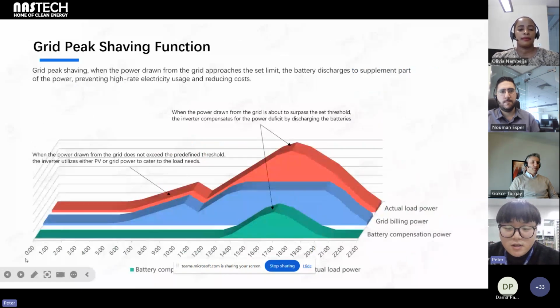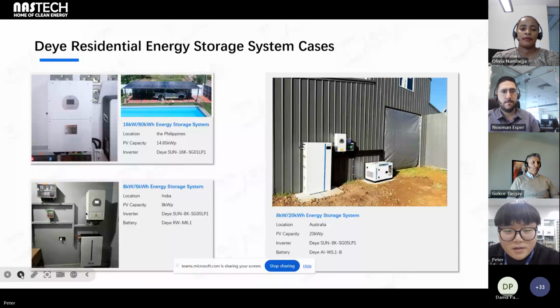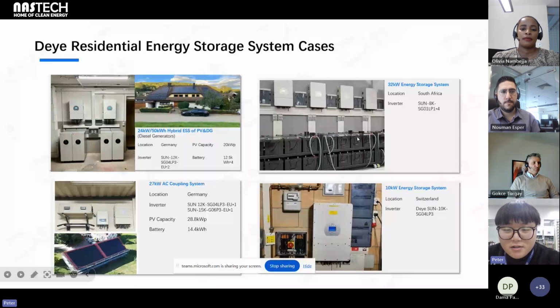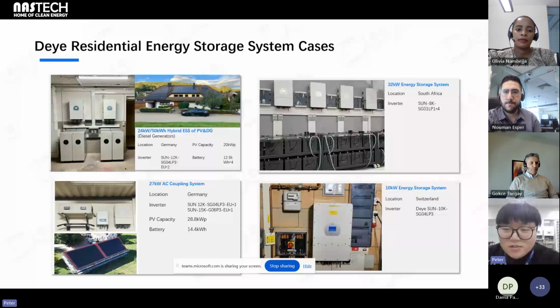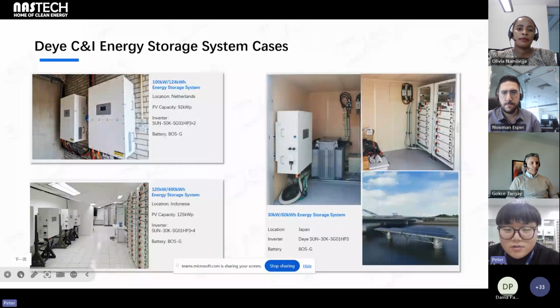And the grid peak shaving function, we can use the PV and the battery to supply your grid peak power, so that your grid consumption can be limited to a lower range, to lower your electricity bills. And here are some cases for the installation. And these are low voltage solutions. This one, we are using a lead acid battery for the low voltage inverter. Actually, it's allowed, but for high voltage inverters, the lead acid battery is not allowed. These are our high voltage solutions, with 50K mostly in these pictures.